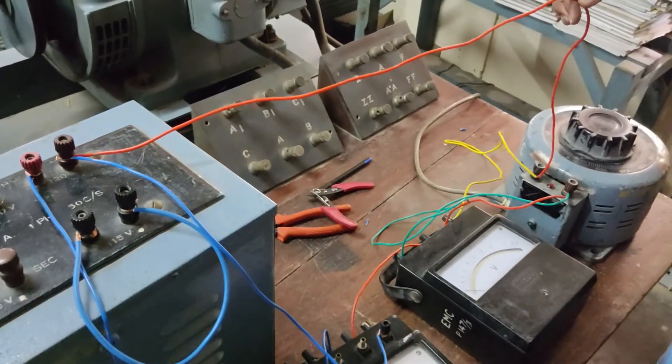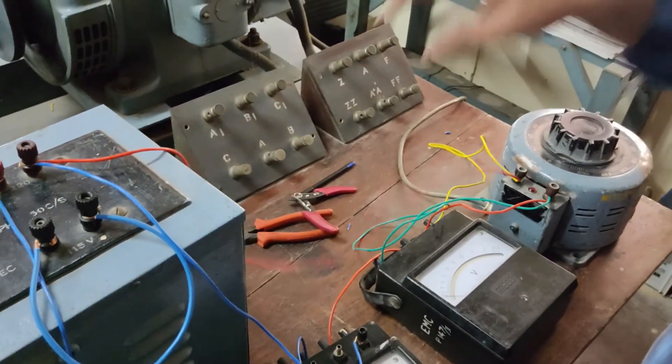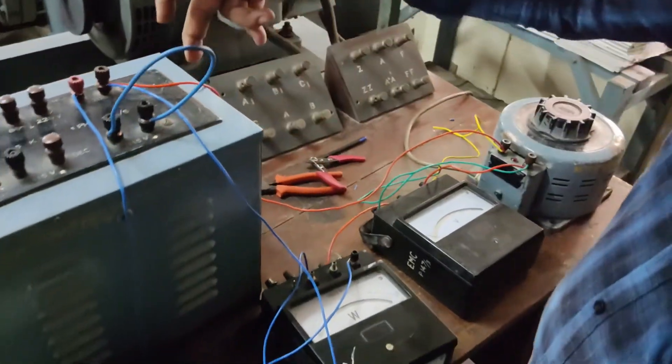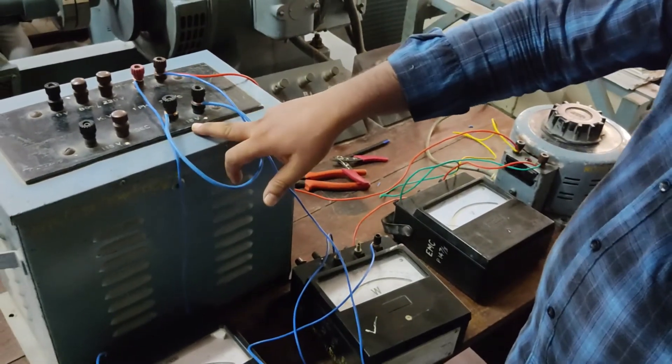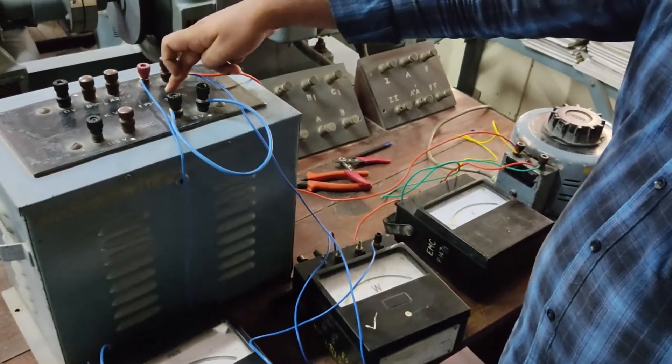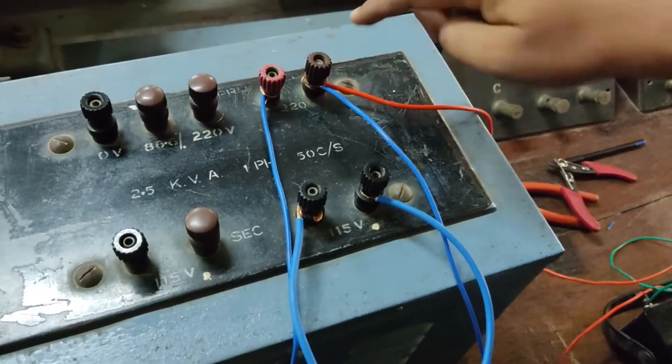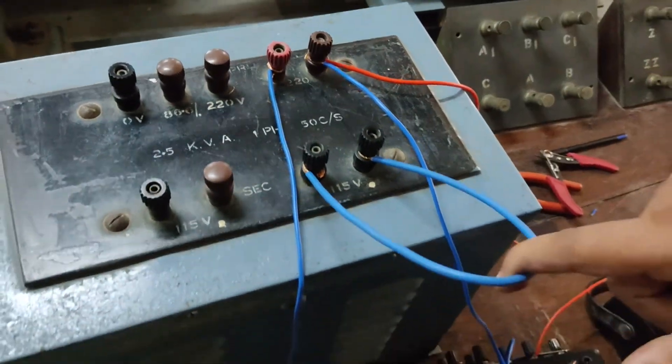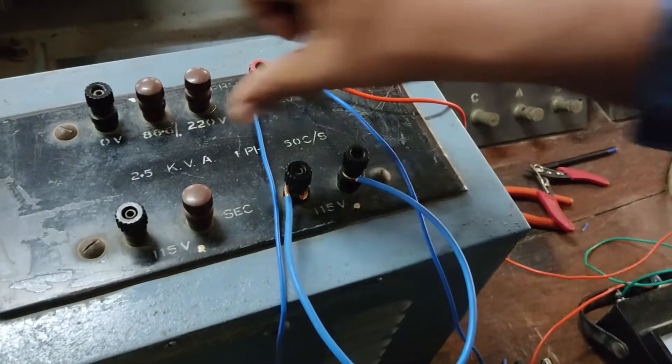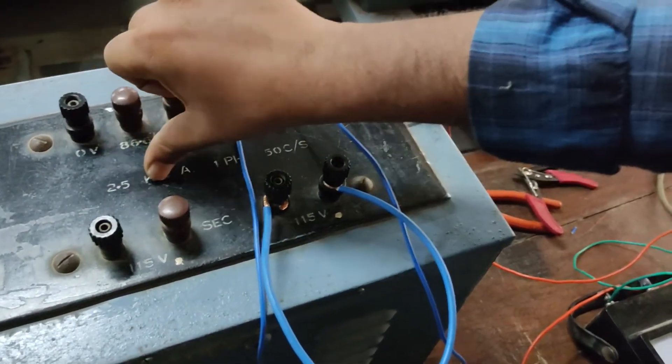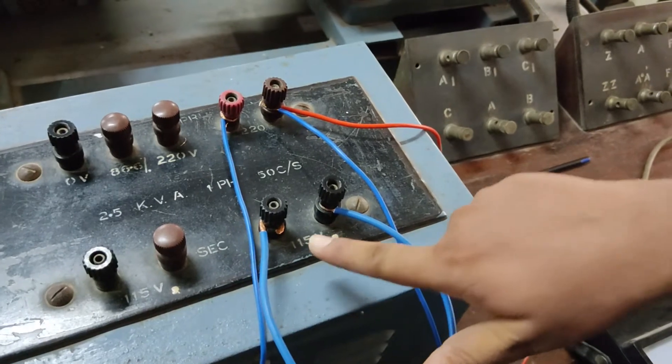For short circuit condition, the low voltage is shorted at 115 volts. Supply is given to the 220 volt high voltage side, and the low voltage side is shorted with a thick wire. These are 2.5 kVA. 2.5 kVA divided by 115 gives the rated current. At short circuit condition it is more than 20 amperes, that's why we have taken thick wire.